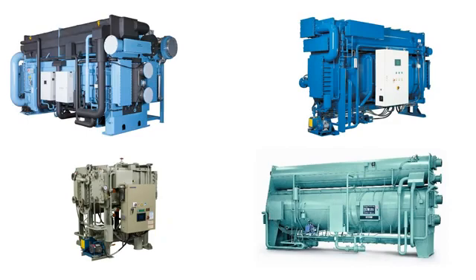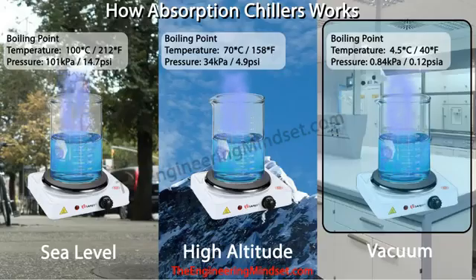So just before we go in and start to look at how the inside of an absorption chiller works, I need you to understand three important concepts for the basic operation of how these type of chillers work. The first point is that when we boil water, it changes states from liquid to vapor. Now the water boils at different temperatures under different pressures. If you increase the pressure, then the water boils at much higher temperatures, and if you decrease the pressure, then water boils at much lower temperatures.